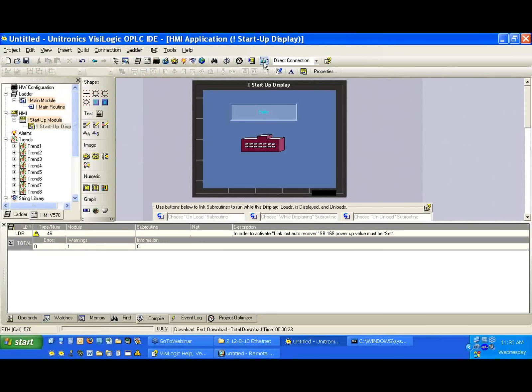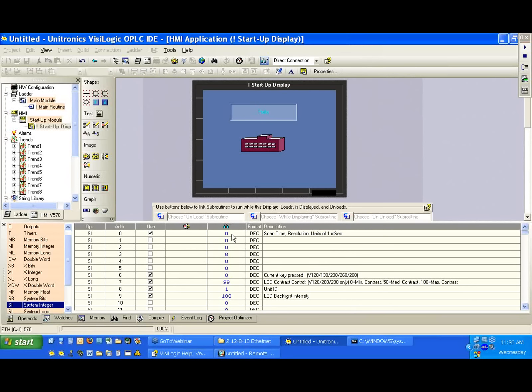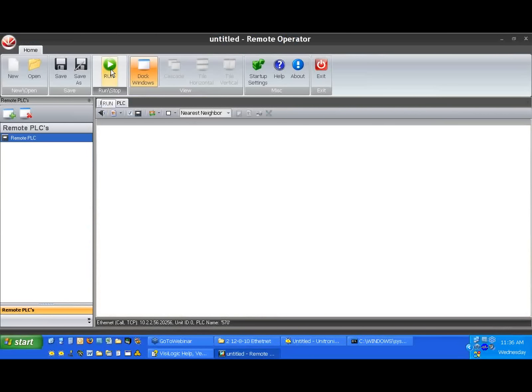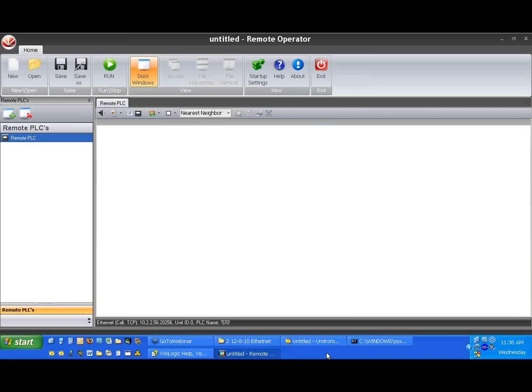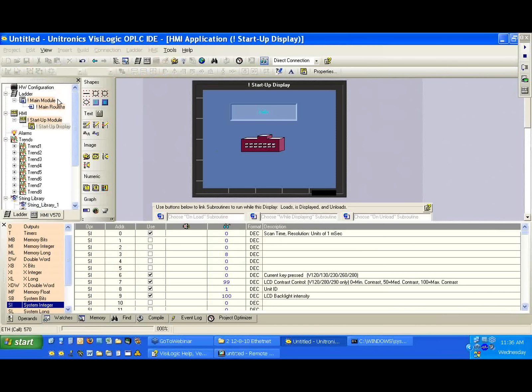Let's do one more test. Let's go online with the controller. We see we are online and can see the online view. Let's try to connect now with Remote Operator. We see we refused the connection. Why did this happen? This happened because TCP/IP, being a handshaking protocol, we can only do one thing at a time. This means if we're using Socket 1, we've connected with VisiLogic to Socket 1 on port 20256.